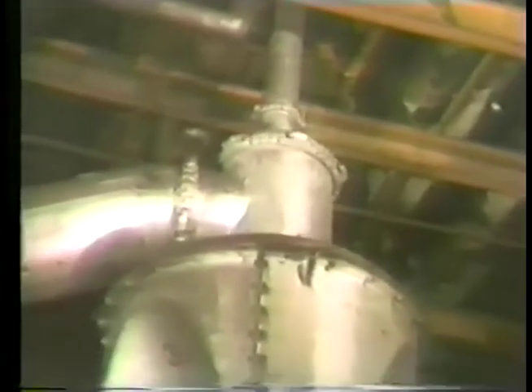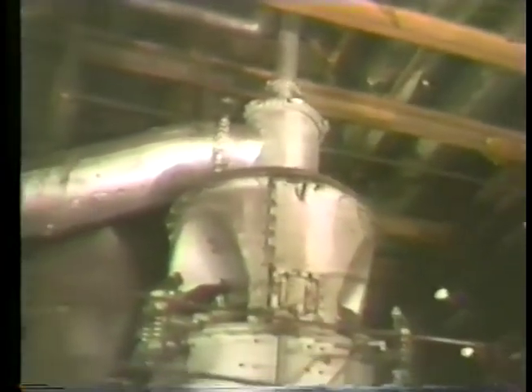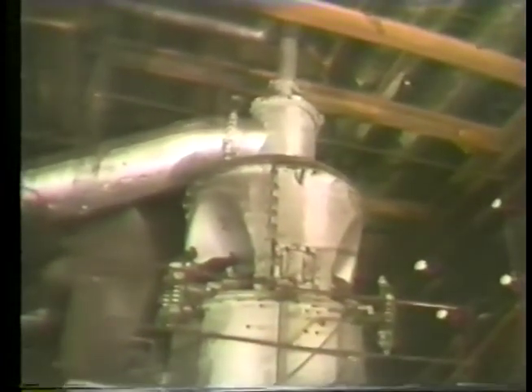When the feeder is shut down, the operators continue to run the pulverizer until no coal is left inside. This reduces the chances of pulverizer fires caused by spontaneous combustion. With these pulverizers, when the pulverizer temperature reaches 100 degrees Fahrenheit, the operator can be sure that there are no combustibles left inside. At that point, the pulverizer can be shut down.